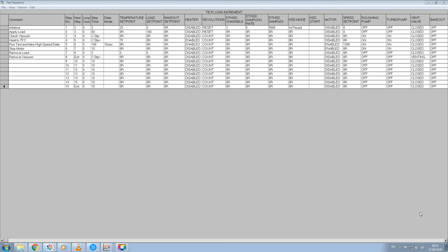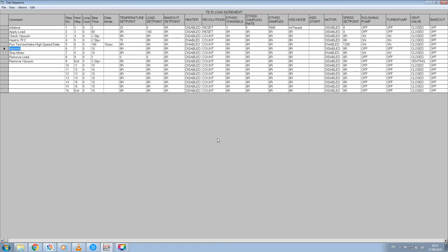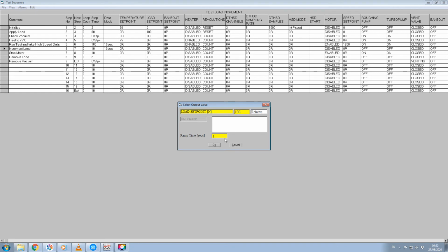To do this, I start by inserting a new step in the sequence. Select the step which is to follow the new step, click on Edit on the toolbar and select Insert New Step. The necessary notes can be added in the comment column and all the subsequent control parameters set, including setting the load set point to 100 newtons relative. A value 100R now appears in the load set point box for the next step. We have to make sure that all the other set points are correctly entered for this new step.